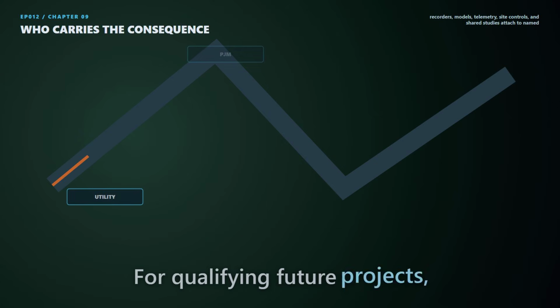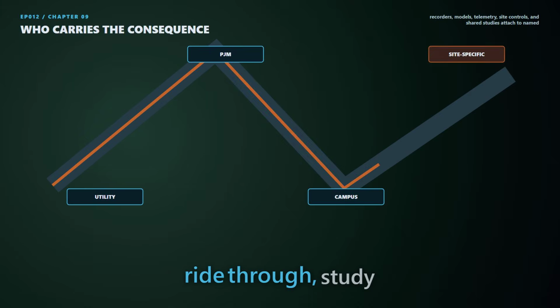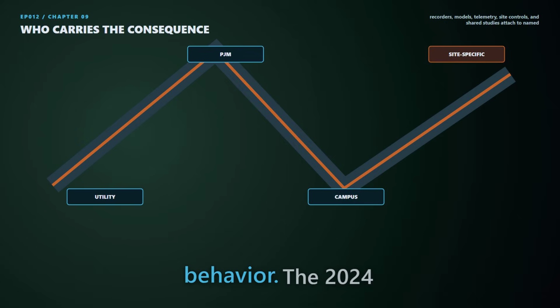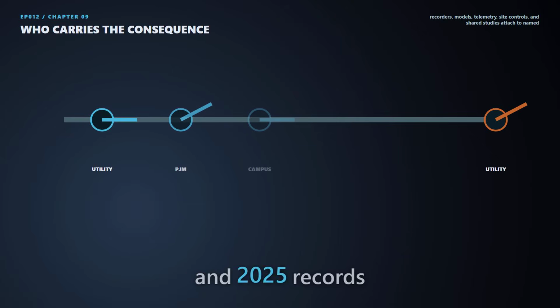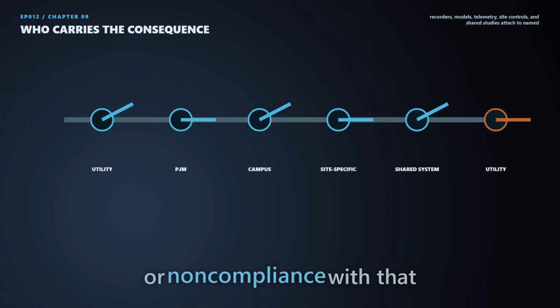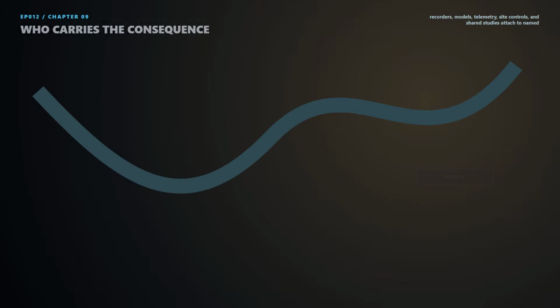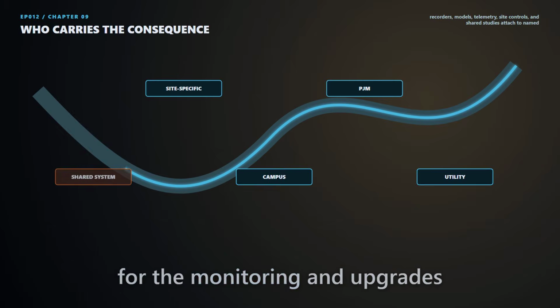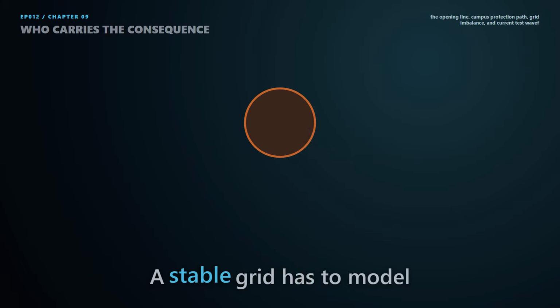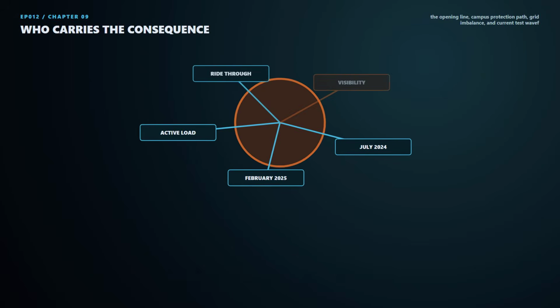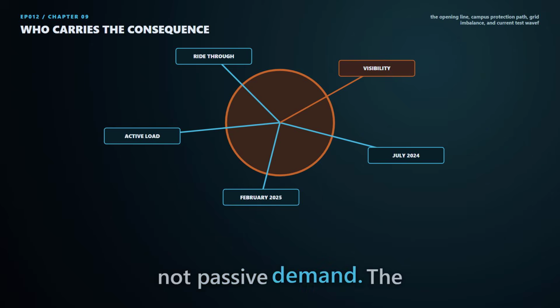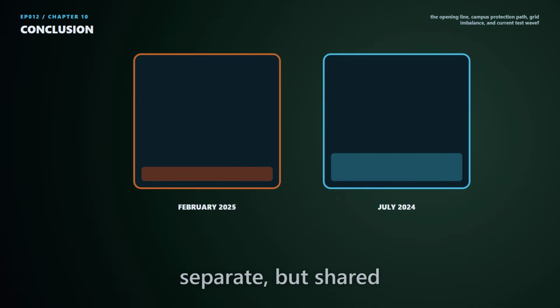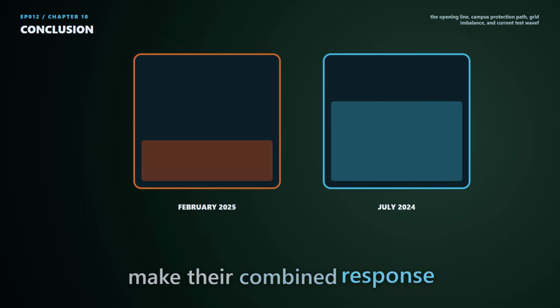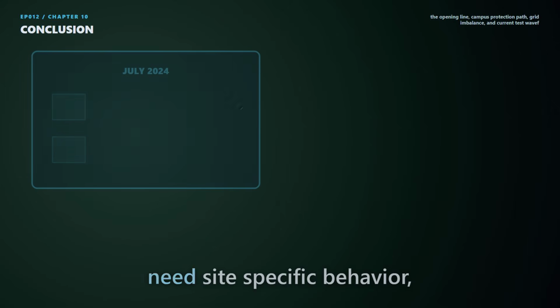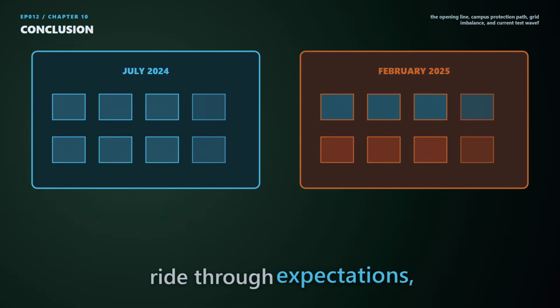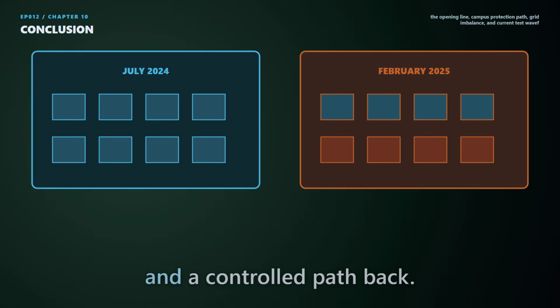For qualifying future projects, Dominion's requirements cover ride-through, study information, and reconnection behavior. The 2024 and 2025 records do not establish compliance or non-compliance with that later standard. Regulators still have to decide who pays for the monitoring and upgrades that coordination requires. A stable grid has to model large data centers as active electrical systems, not passive demand. The buildings and owners remain separate, but shared voltage thresholds can make their combined response look like one machine. Planners need site-specific behavior, ride-through expectations, visibility during a transfer, and a controlled path back.